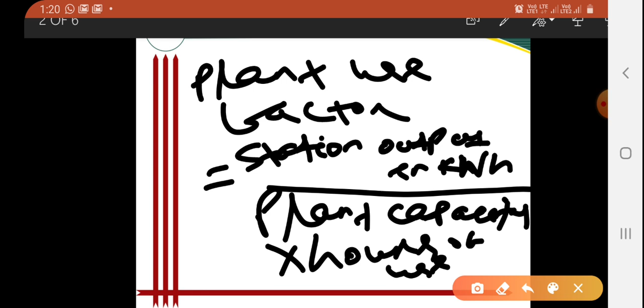So for example, you can understand, suppose the installed capacity of a power plant is 20 megawatt and the annual output is 7.35 into 10 to the power 6 kilowatt hour. So this is the output which is produced from the plant in an annum. But the operation hours in a year is given as 2190 hours. This is not 8760 hours per year. So if the operation hours is 2190 hours, then when you have to calculate the plant use factor, we have to consider 2190 hours only.